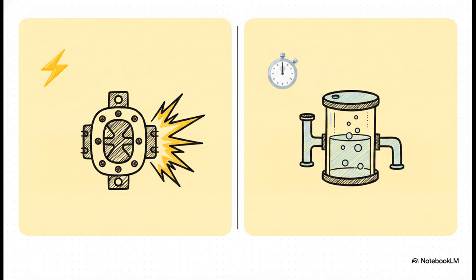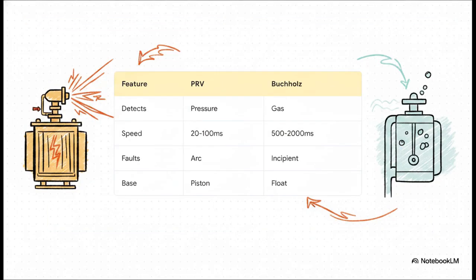Basically, the PRV is your rapid responder. It's there for those sudden, violent internal arc faults that cause immediate pressure spikes. The Buchholz, however, detects slow, incipient faults, like slow insulation degradation or core faults, by measuring dissolved gas production. But here's the kicker. Because those gas bubbles take time to collect and trigger a mechanical pendulum through buoyancy, the Buchholz can take up to 2 full seconds to trip. That's 500 to 2,000 milliseconds, compared to the PRV's 20 to 100.